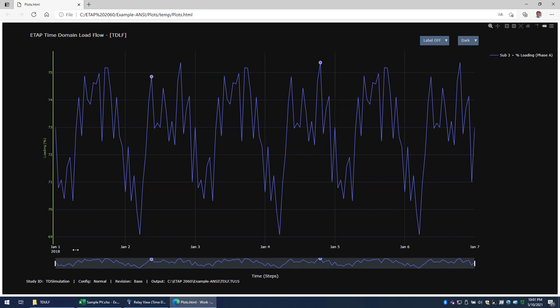Here's the graph. You can see on the bottom, starting from January 1st, January 2nd, this is the x-axis, January 3rd, all the way through January 7th. On the y-axis, we have the loading in percentage. As you can see, between the solar PV, the wind, and also the loading over time, you can see the different loading profiles. These dots are essentially the events, right? On January 2nd, we open a circuit breaker, and here on January 4th, we did an impact of a lump load. So it's a very clean and very professional way to export your reports.